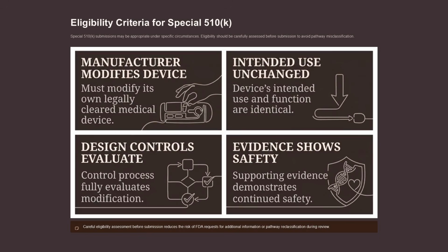Special 510(k) submissions must meet specific eligibility criteria. Eligibility is carefully assessed to ensure that modifications are minor and do not affect the device's intended use or safety. Design control processes must effectively evaluate the modification, and supporting evidence must demonstrate continued safety.